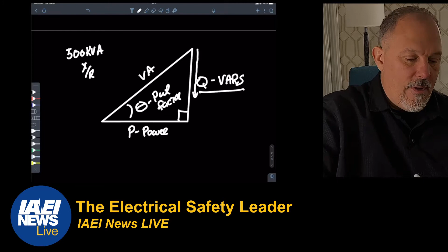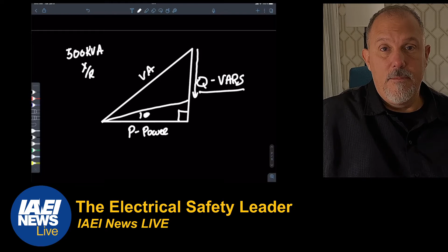So I've taken my power factor, my theta, my angle, and made it smaller by adding capacitance into the system to correct power factor, to get as close to unity as I can. You want to be probably around 0.95 power factor. This is the practical application of this triangle. Before we get into the math, I want you to at least understand that.